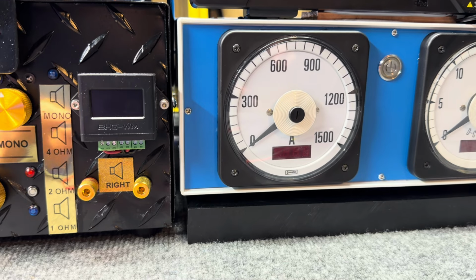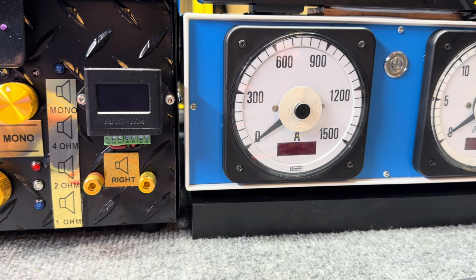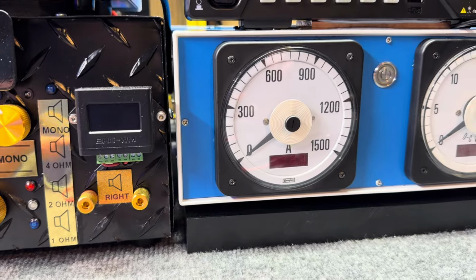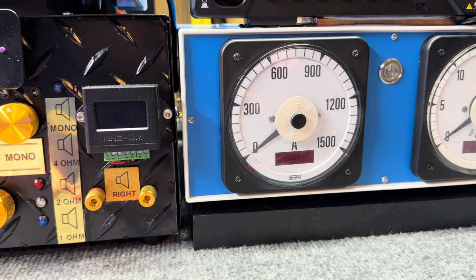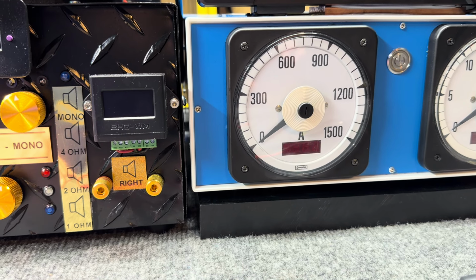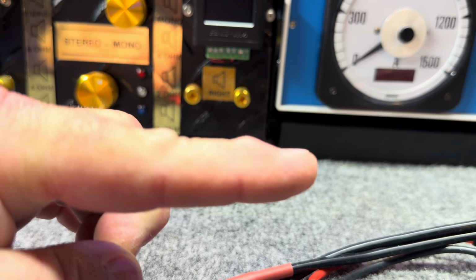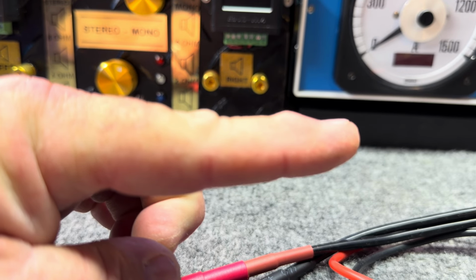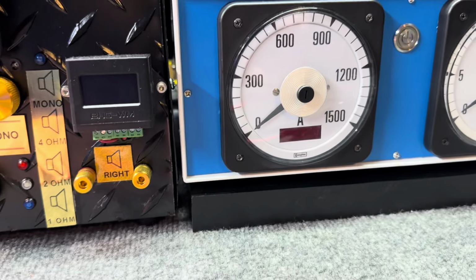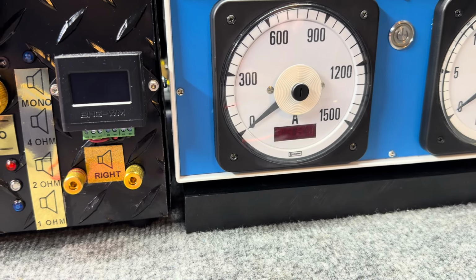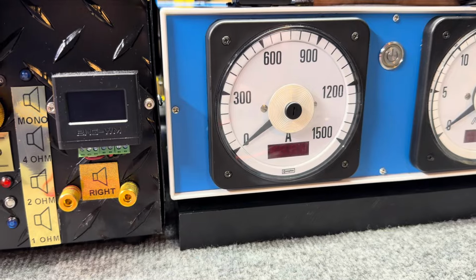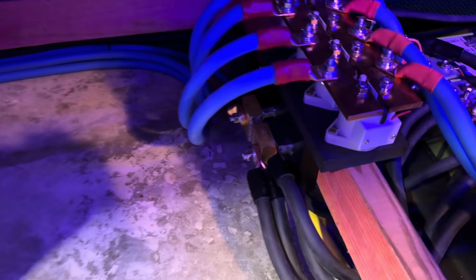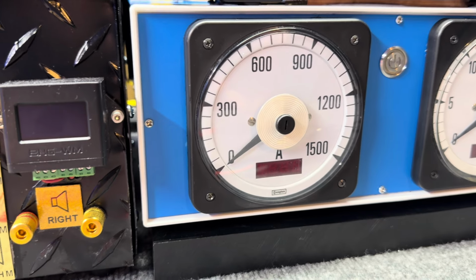On DC, not AC, the DC clamp meter is fairly accurate, but not super accurate. There's some things to consider, like extra magnetic fields - you constantly got to zero the damn thing. Whether the wire's going through it, it's best to have it through the center and directly at a 90-degree angle to the clamp to get the best current reading. Any moving around can change it significantly. So the most accurate way to read DC current is with a damn shunt, because it's calibrated to give a certain voltage drop for a certain amount of current.